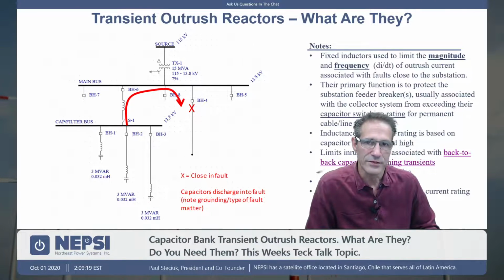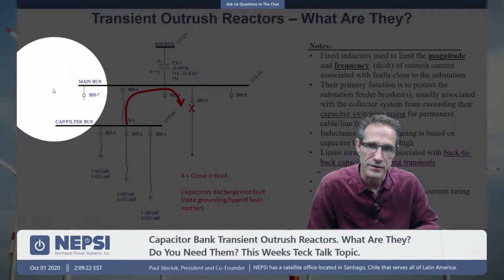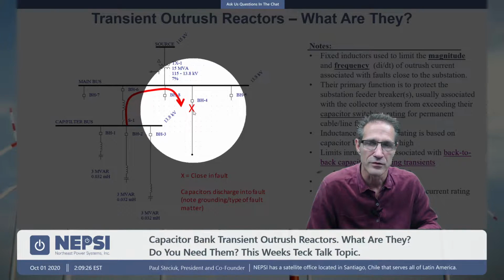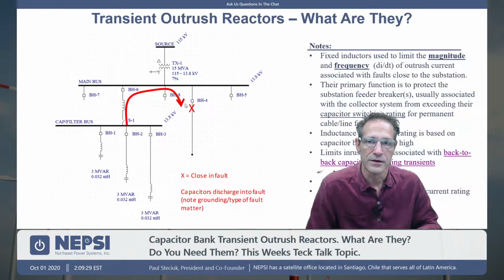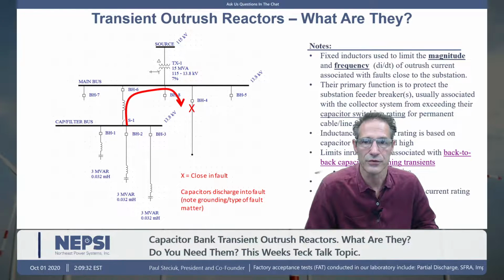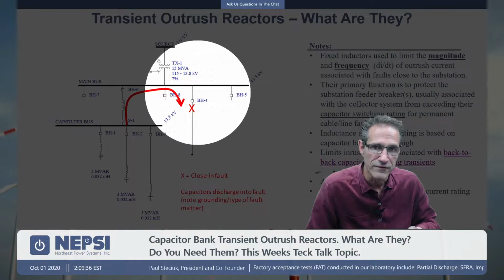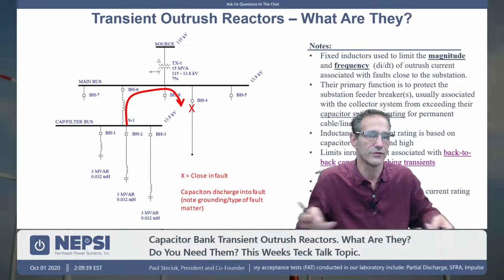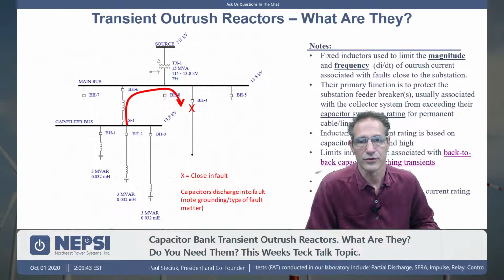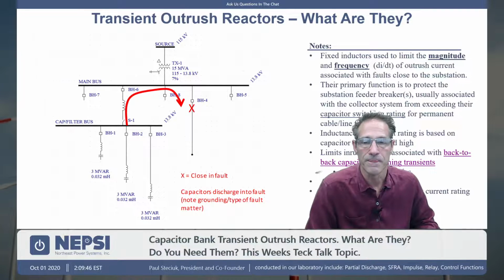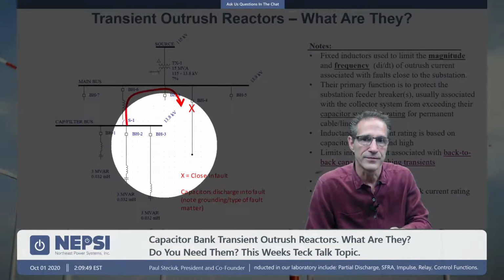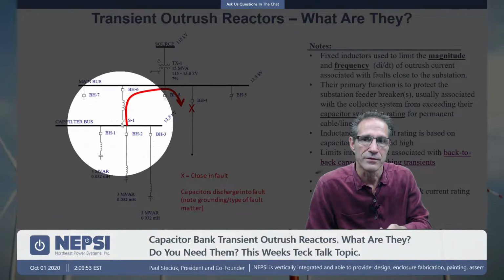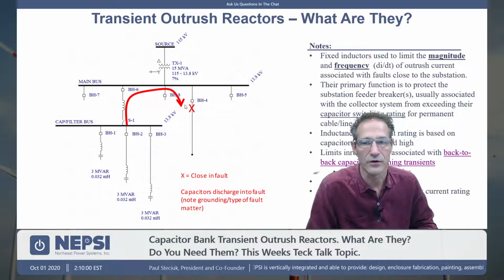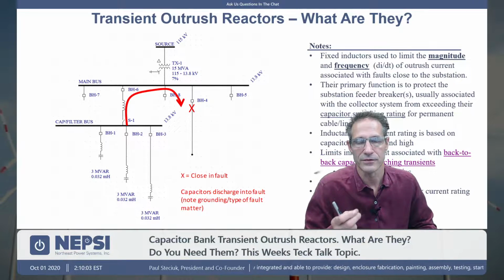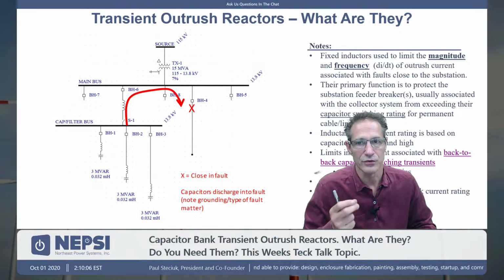So what we have in this situation is if we have a fault, and I want you to think about this, and this is kind of a complex concept. If we have a fault over here, where this X is, and the capacitor bank was operational, BH1, 2, and 3 were running, and this breaker, which is a feeder breaker to, say, a collector system, so you say you have a string of wind turbines, and those wind turbines are strung together with the cable coming out of BH4. If we had a fault somewhere on that system, the breaker would be closed, and the capacitor bank, because this was a faulted circuit, it would want to discharge into that fault. Now that's not in itself an issue. Typically there is no issue with that first initial fault condition.